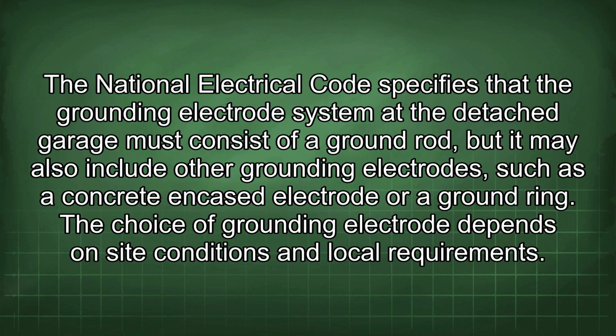The National Electrical Code specifies that the grounding electrode system at the detached garage must consist of a ground rod, but it may also include other grounding electrodes, such as a concrete encased electrode or a ground ring. The choice of grounding electrode depends on site conditions and local requirements.